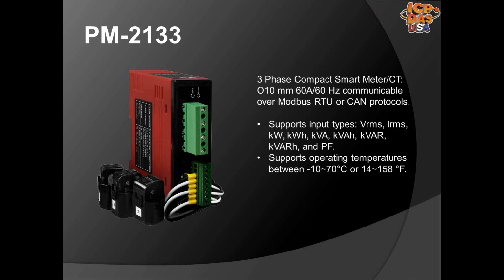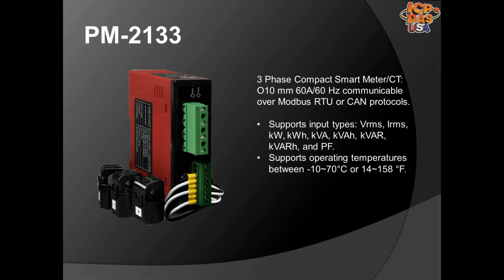PM2133 is a 3 phase compact smart meter communicable over Modbus RTU or CAN protocols. They are DIN rail mountable, and you can daisy chain Modbus RTU devices over RS485 with 2 copper wires. RS485 networks support up to 255 devices in one network and support communication distances up to 4,000 feet.